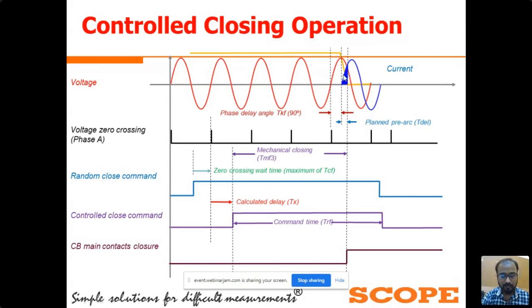Now we can see the control switching device executed the control close command to the CB. At this moment, you can see this dotted line where the CSD executed the command to the CB contact, and from this point to this point is the mechanical closing operation, the mechanical closing time of the circuit breaker. That is the closing time of the circuit breaker.